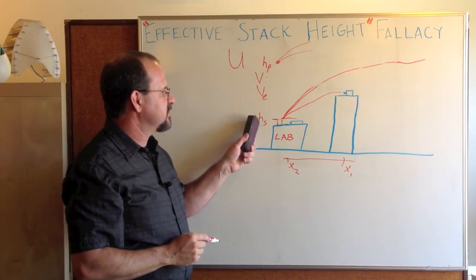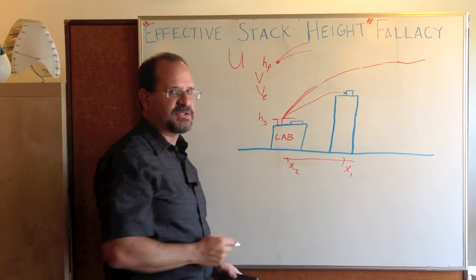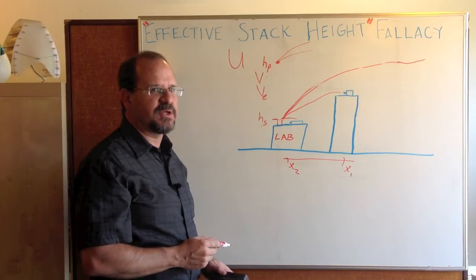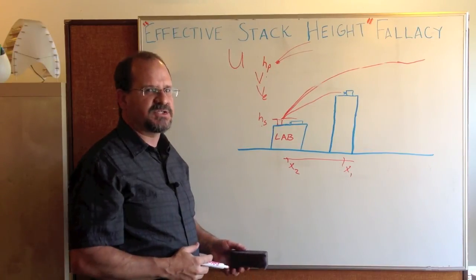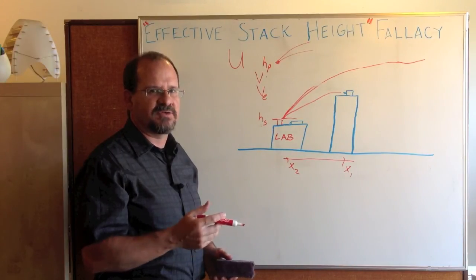You use your physical stack height, your volume flow rate, your exit velocity, the distances to all your air intakes that you're concerned with, run through all the equations, make the necessary adjustments to your design, and you'll have good air quality.